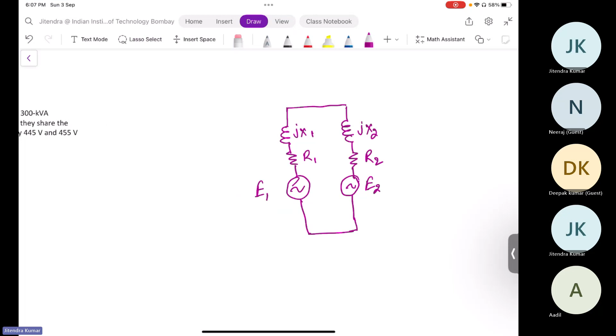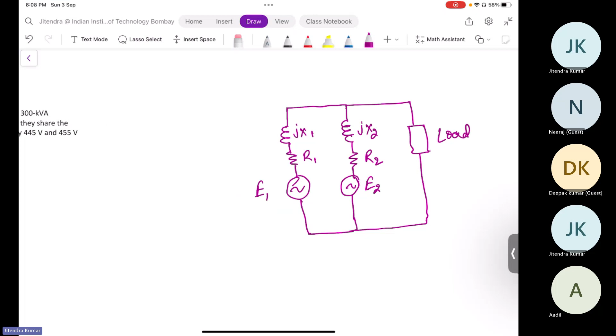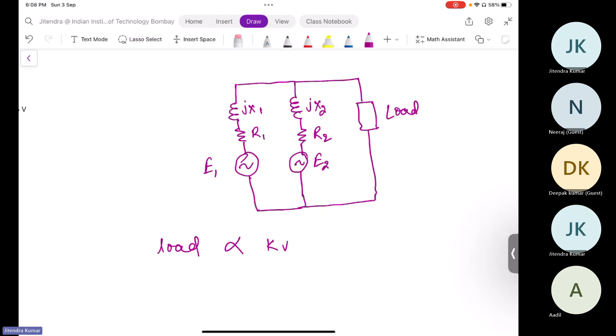Now how to provide this load, and in what ratio should these two transformers operate such that any one of them should not get overloaded. These are the primary concerns, such that one case arises where the load becomes directly proportional to the kVA rating of the transformer.